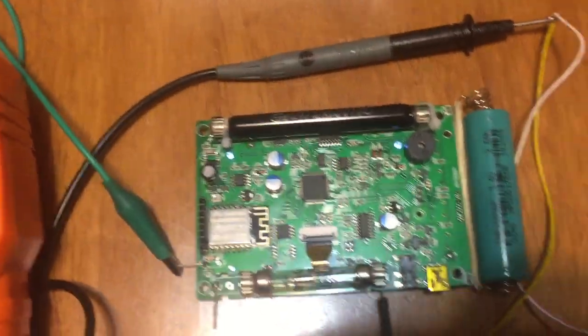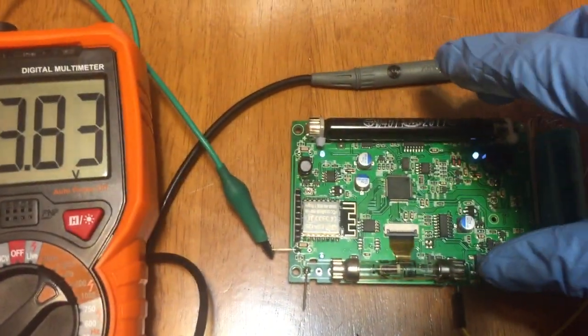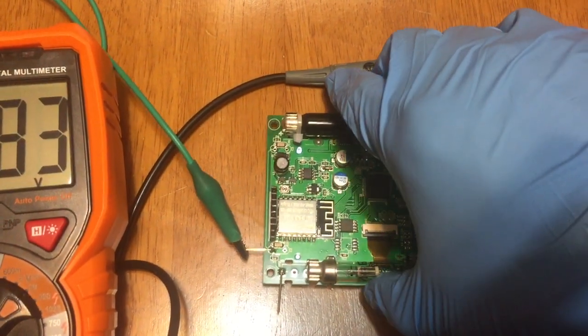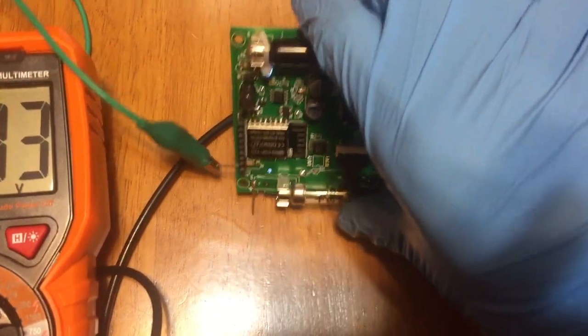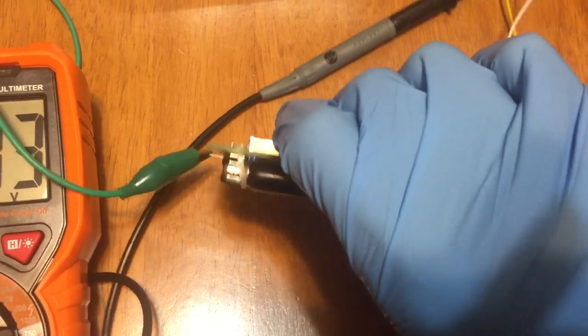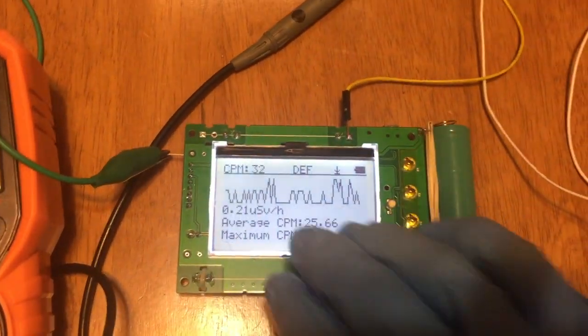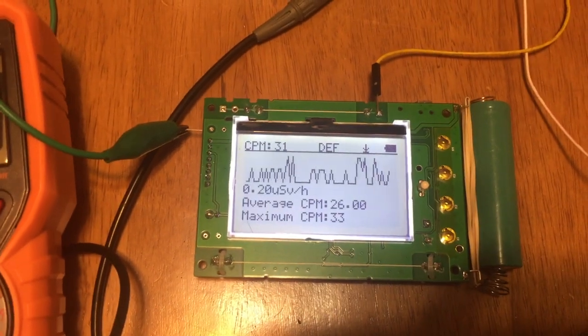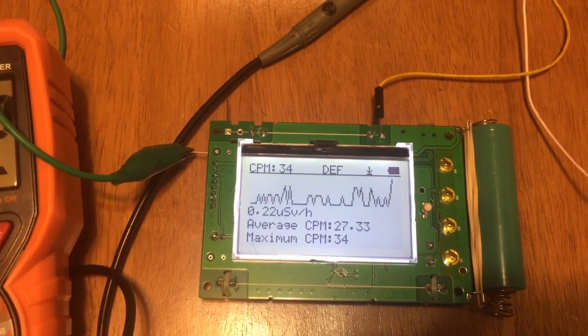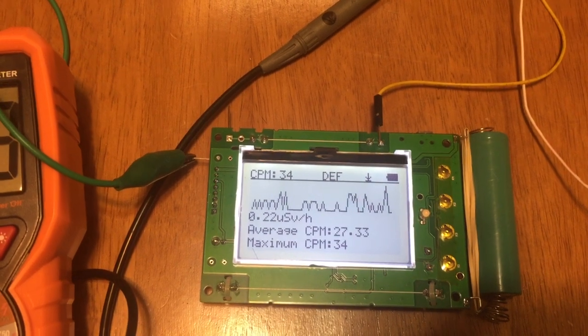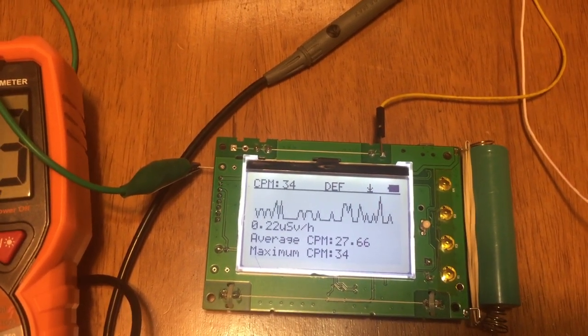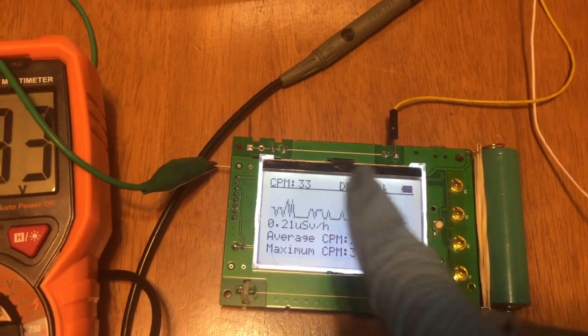I'm going to test both tubes. First testing is on the onboard tube. I'm turning it over and setting the display to graphic mode because I can easily see how long time has passed to one minute for the testing. Also I can get the maximum CPM here easily.